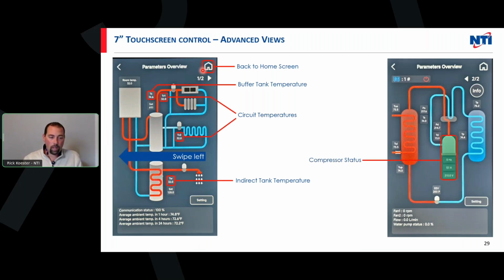So now we can get more data. We can see our compressor status. It's going to tell us our frequency, amperage, and voltage. We can see the entering and leaving water temperatures, so now we can get an idea if we have a circulator that's properly sized and if we're getting good heat transfer through it. We can tell a lot from these numbers, delta T. We're also going to see our refrigerant pressures.